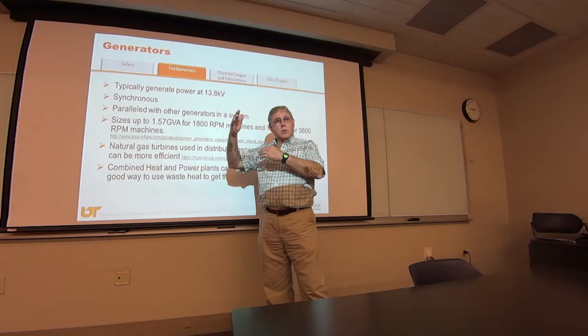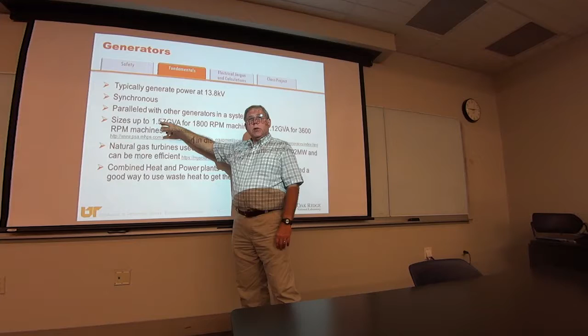Big, 1.57 gigavolt-amps. Volt-amps is the way you size electrical gear, not watts. You size chilled water plants and mechanical stuff based on watts because that's dealing with real work. Volt-amps is watts plus some other stuff that goes on in the electrical system that doesn't do work. But that's a pretty big, that's a 1,570 MW or MVA generator, and they're as big as this room. They're huge. I mean, they're very, very huge.